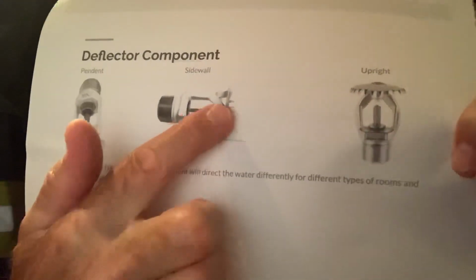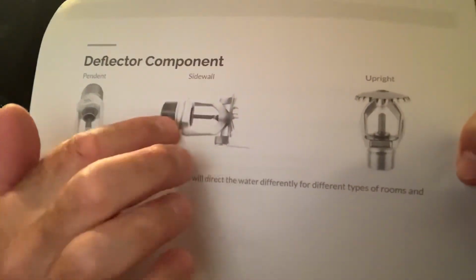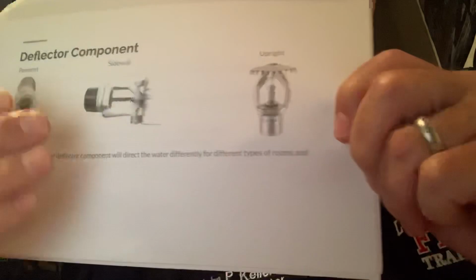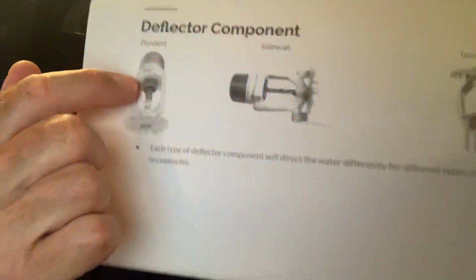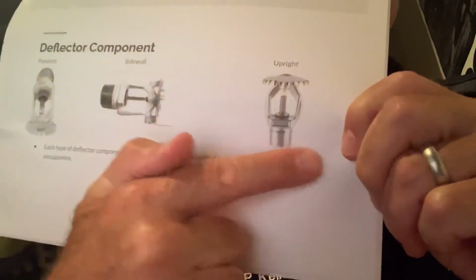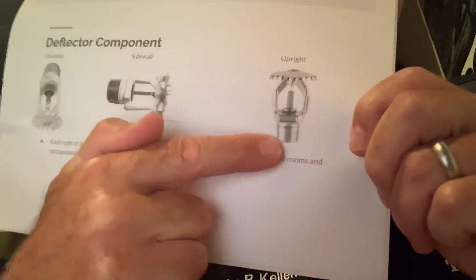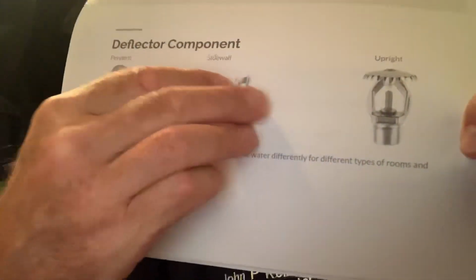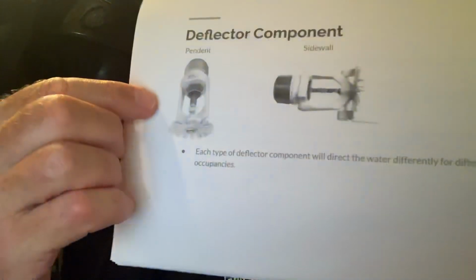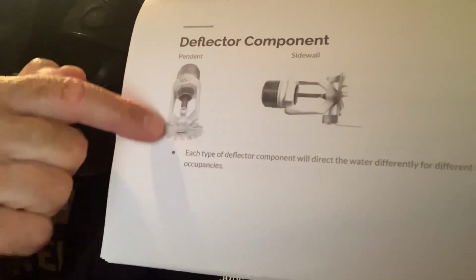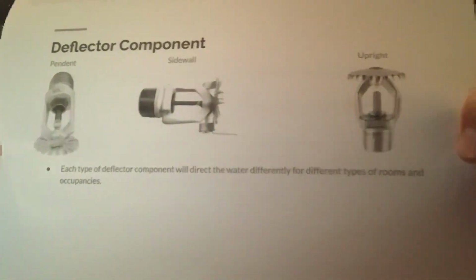Your deflector component. Here's different types of sprinkler heads. There's your pendant. Okay. There's your sidewall, meaning it's on the side of the wall. Okay. And look at the deflector component. A lot of hotels have sidewall components. They're on the side of the wall, just hanging on the wall. And then your upright sprinkler head, notice the deflector component on the upright is different than the pendant, okay? Upright means your piping, your branch line right here, is off here, and the sprinkler is upright. So the water will spray up, deflect back down. Your sidewall will spray out and then deflect off this deflecting component and spray outward. And then lastly, this pendant is hanging downwards. Okay, here's your piping here, branch line. And then water will spray and then deflect off this deflecting component, different than this one over here. Okay, see you guys the difference?